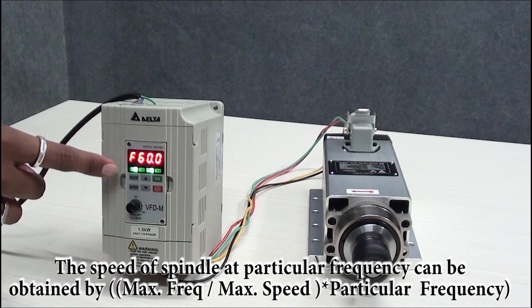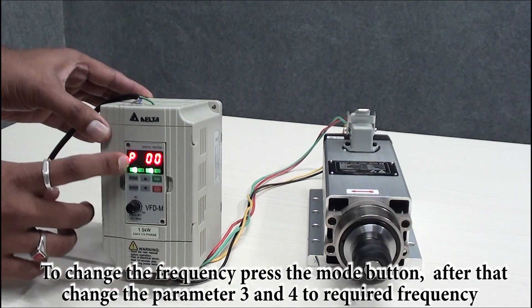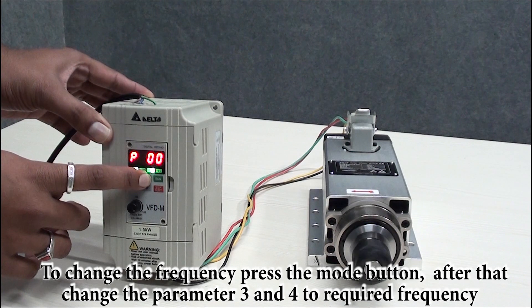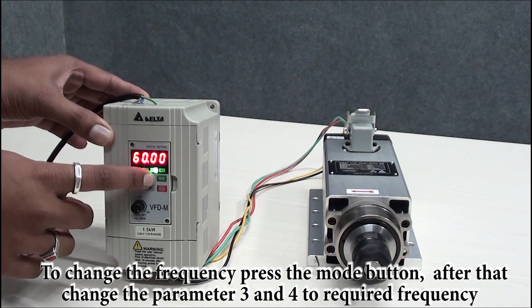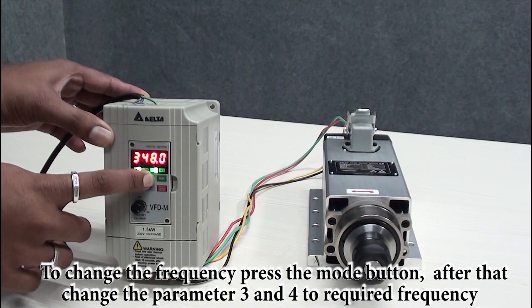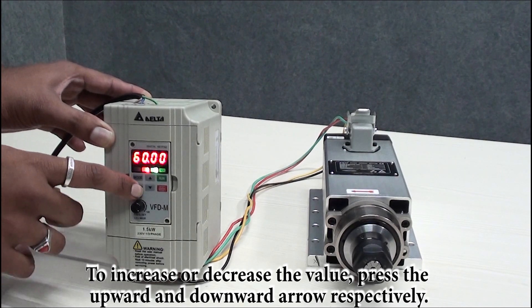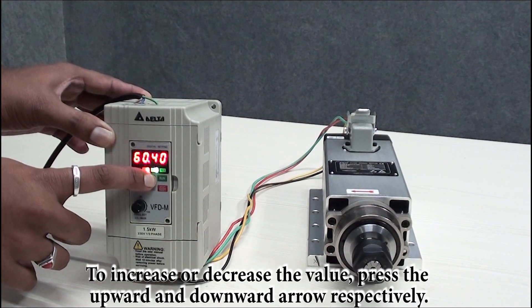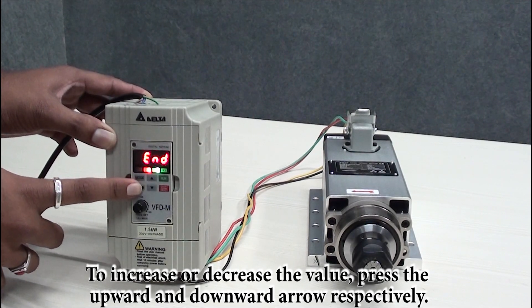Now how to change the parameter: press the mode button. P is for the parameter. Go to parameter 3, press enter. This is 60 hertz by default. Now you can increase this to 400, press enter. Then same parameter 4, press enter which is 60, increase to 400, then press enter.